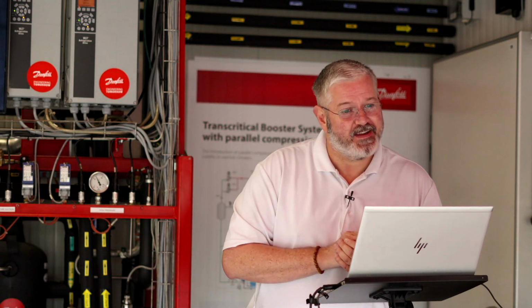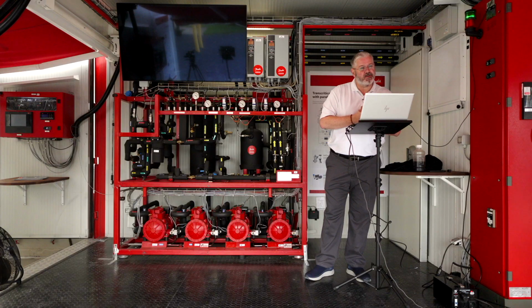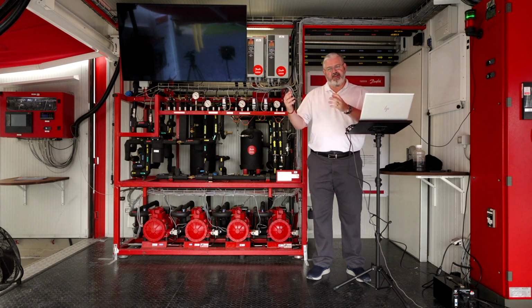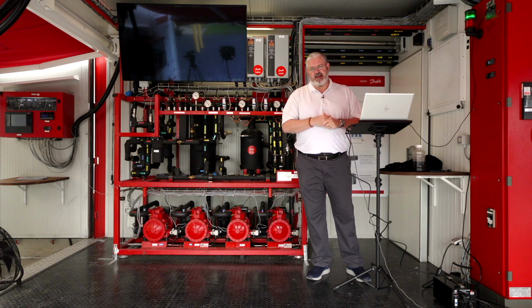Do you have any data on expected percentage of refrigerant loss per year on a CO2 system? I don't really have data on that. My guess would be the same people that put in the CO2 are the ones that put in the HFC. Whatever percentage leaks you see on the HFC, you probably see about the same on the CO2. Probably a fair guess.